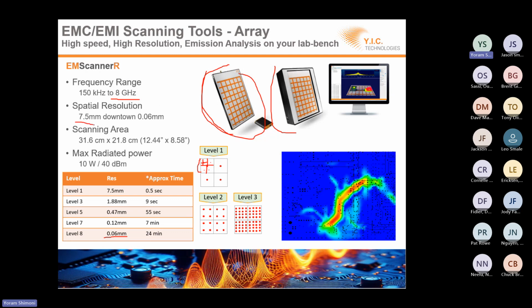And again, the spatial resolution, the native resolution, is 7.5 millimeters all the way to 0.06. The scanning area is something like an A4, a printer page. We do have requests specifically from car manufacturers and people who design really, really big boards, if we can address that. And the answer is yes, but it's getting very expensive for very big scanners. The way that we do that is we can either move the scanner, and that's the cost-effective solution, or we can connect multiple scanners together with an RF switch, and then the software will stitch everything together. That will be the best solution from a signal integrity point of view, but it will introduce very high cost to that solution.